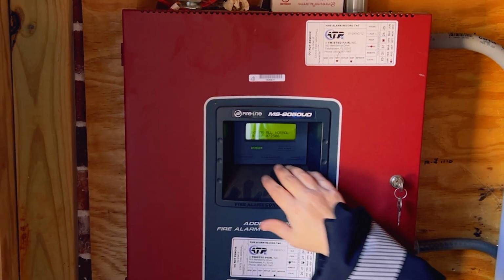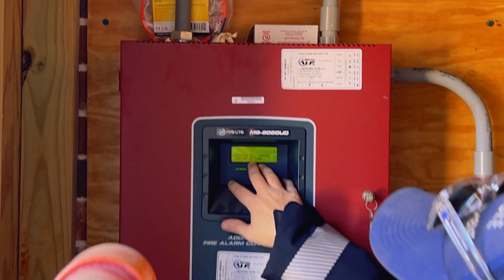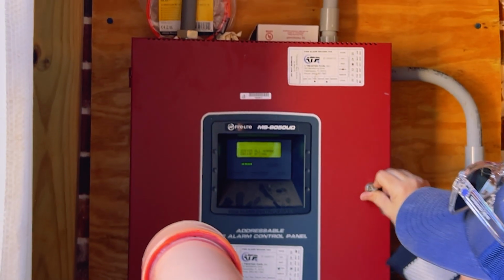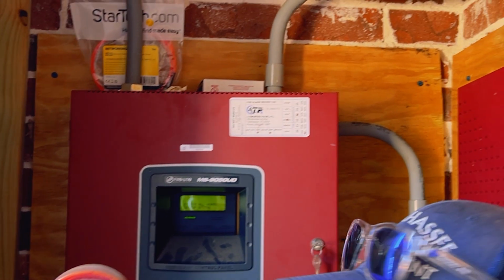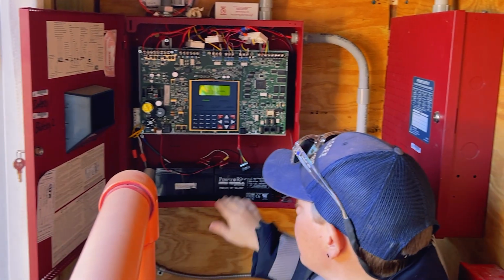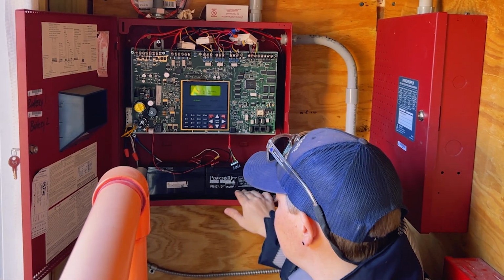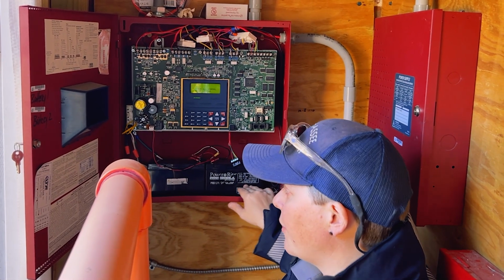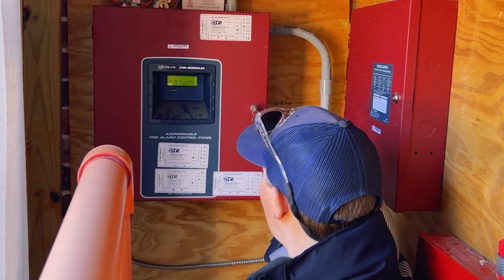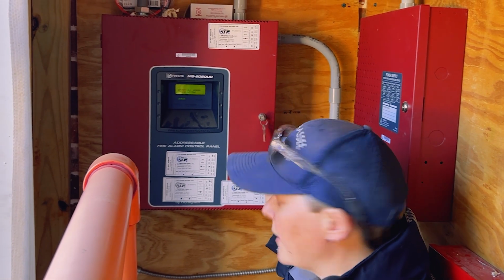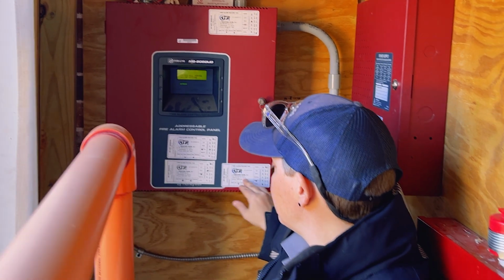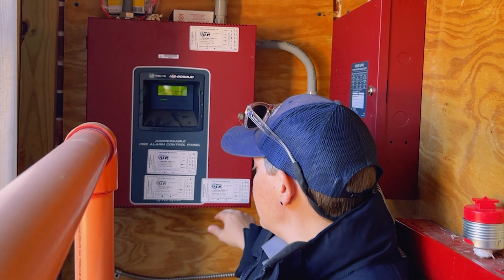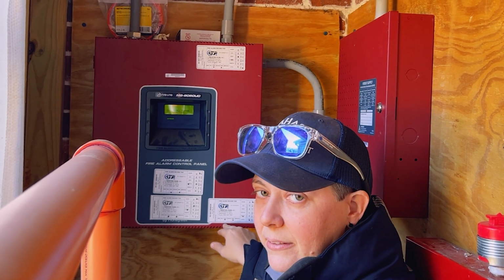With this fire alarm right now, it says system normal. So that's what I'm looking at. I want to make sure that there's a key or I have access to a key. I want to make sure that the batteries have been inspected and they have an expiration date on them. Everything expires. And then I'm also looking for an annual inspection tag by a licensed company. So I check that, check my dates and what they did. They came out and they did an annual inspection.